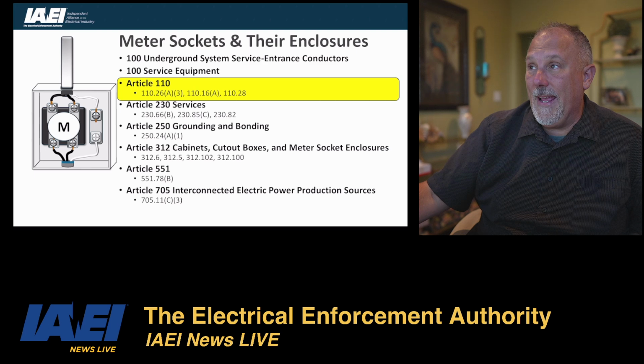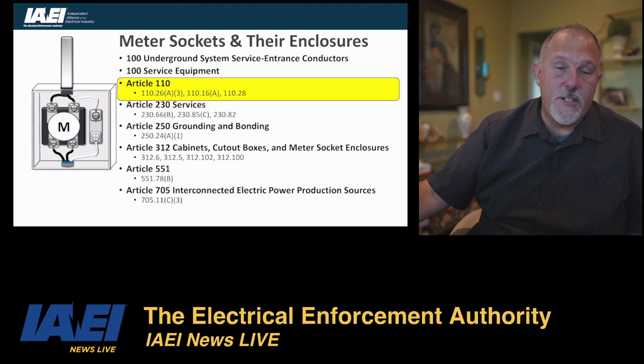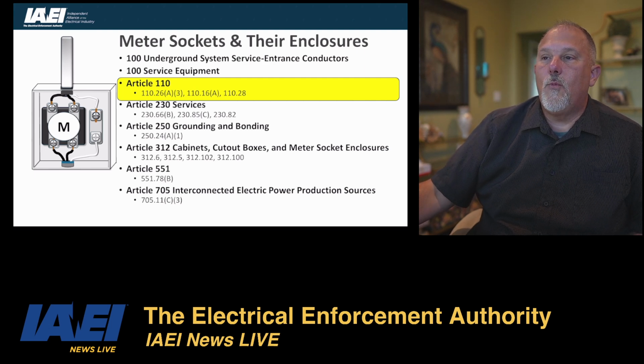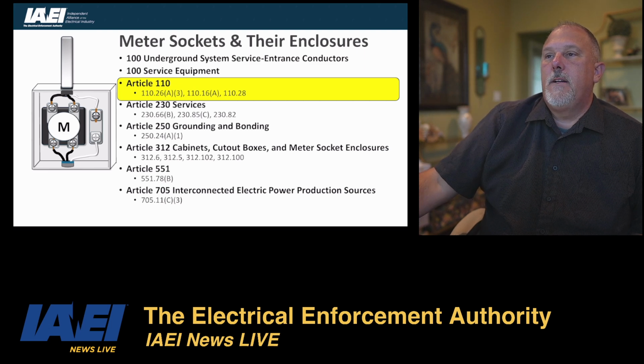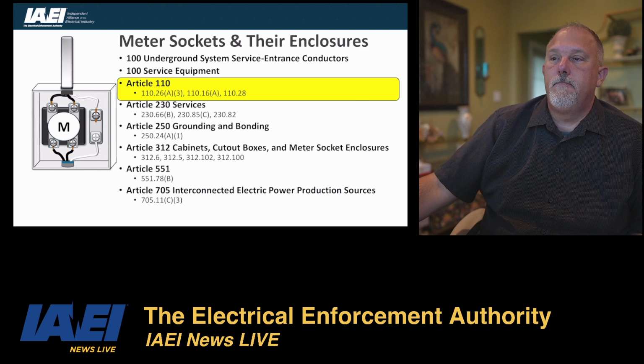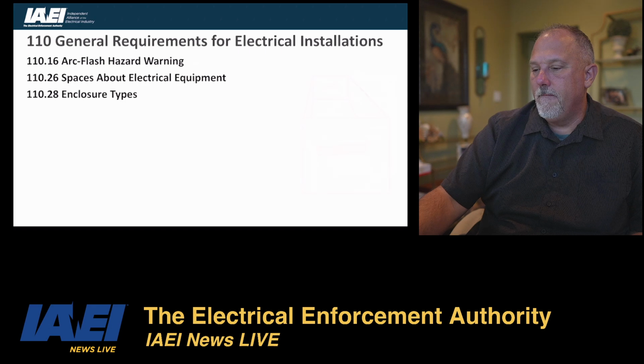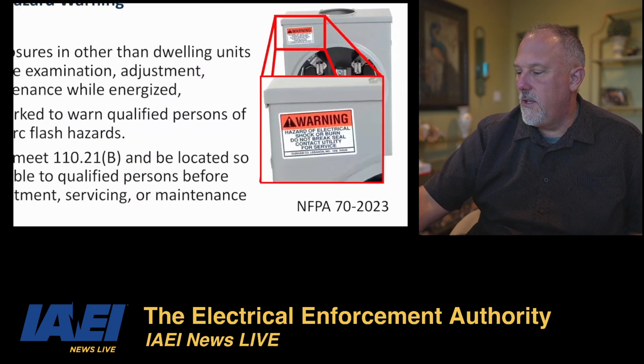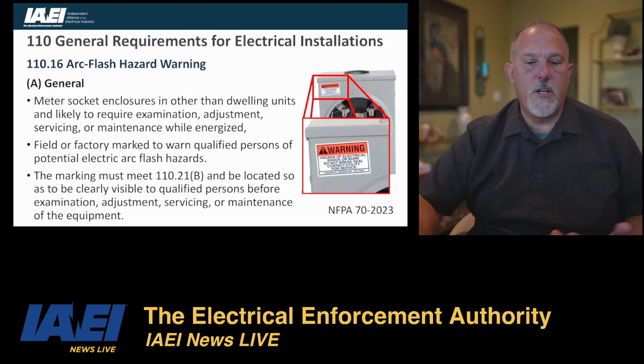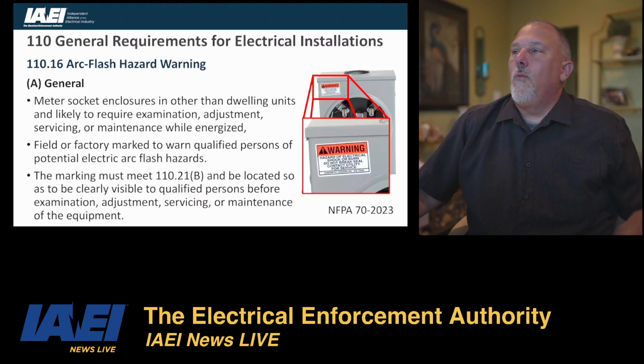Can't forget about Article 110. Now, there are a lot of different requirements in Chapter 1. Remember, Chapters 1 through 4 apply generally. Now, in 110, 110.10 will be the short circuit current rating. 110.24 is your available fault current marking. 110.16 is your arc flash label. And in 110.16, you'll just need a hazard marking, right? So remember, that's that generic marking that the hazard of electrical shock or burn, do not break seal. That's your motherhood and apple pie label, I call it. That's your 110.16(A).